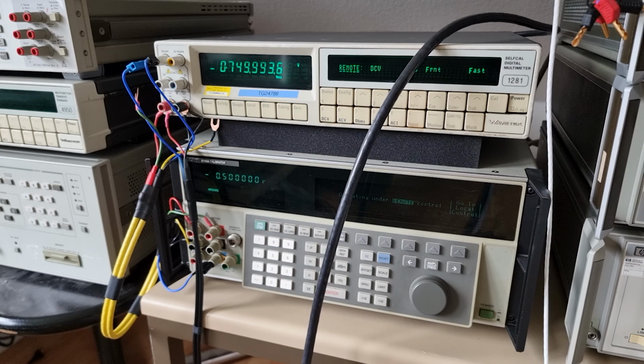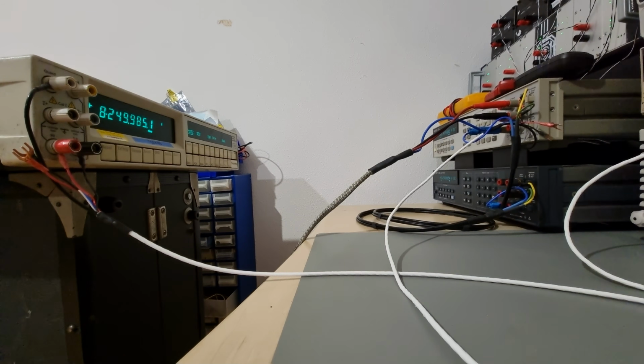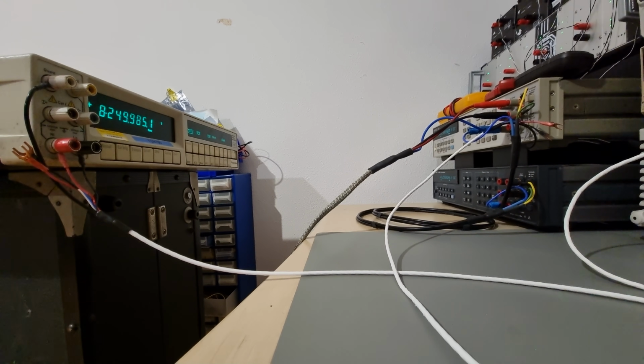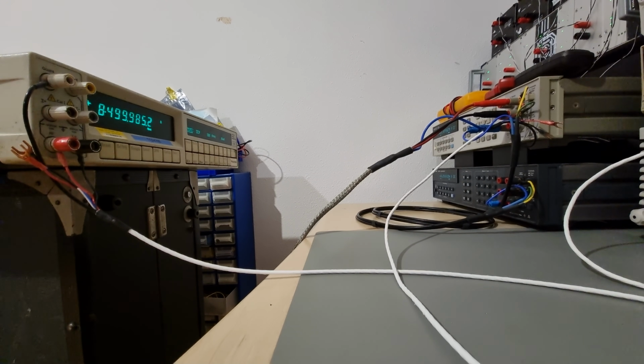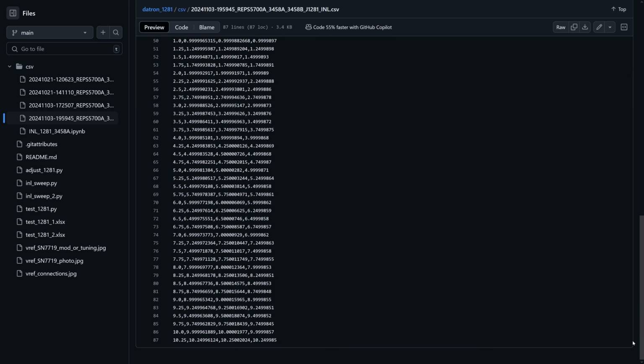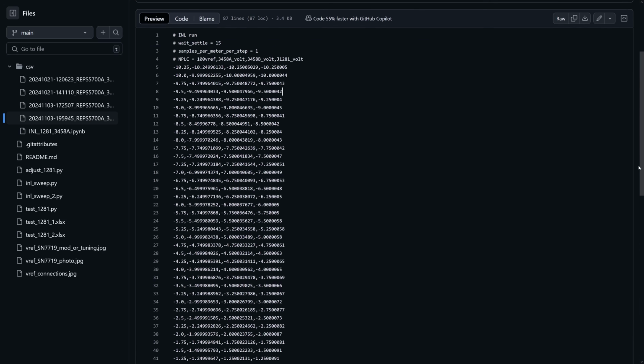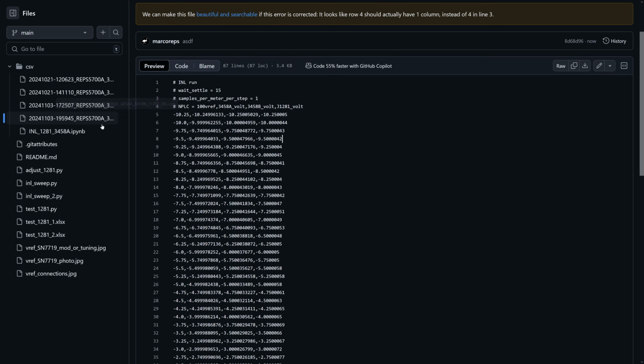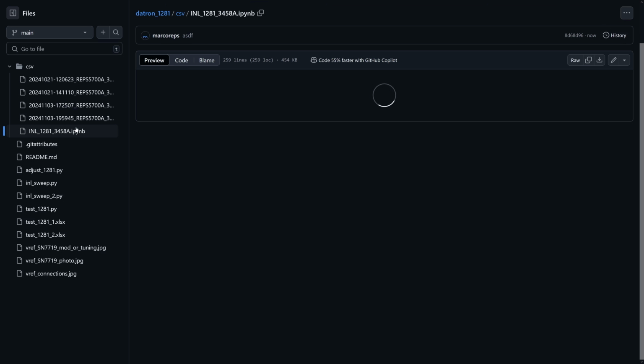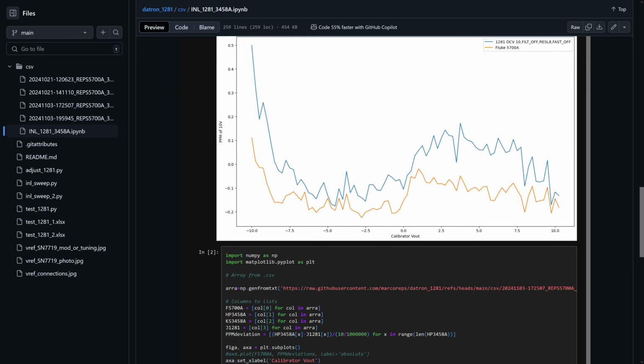I'll consider this job done, but we still have a couple of minutes before this high-profile patient needs to continue on its journey. So I set up a couple of DC voltage sweeps to be observed by 3458As and Datron 1281. The raw results are linked below, but my TLDR so far would be that Datron's integral linearity is within 0.2 ppm of the best linearity that my lab has to offer.